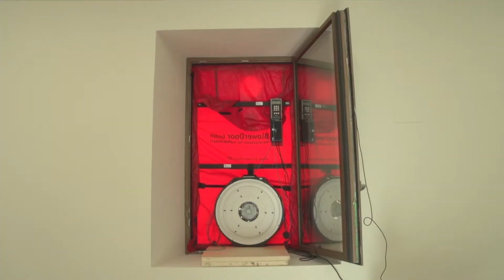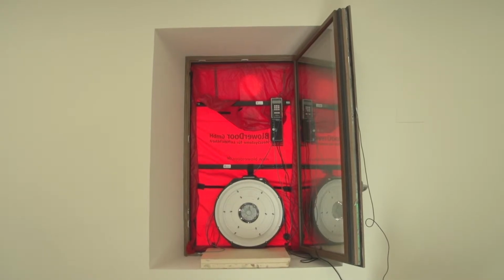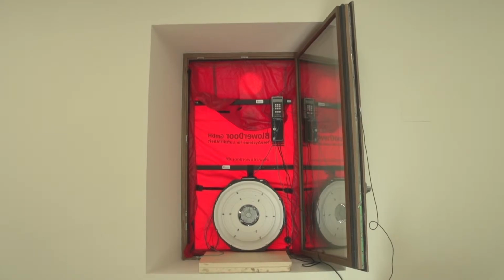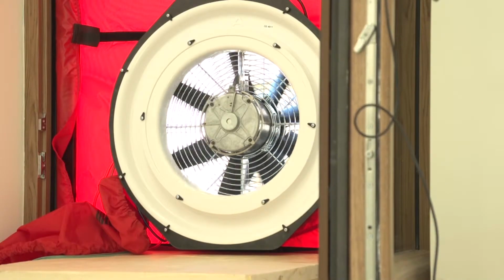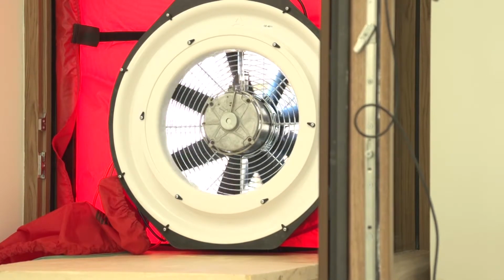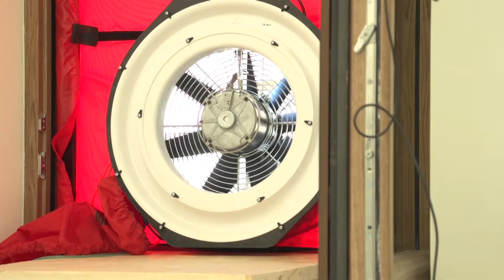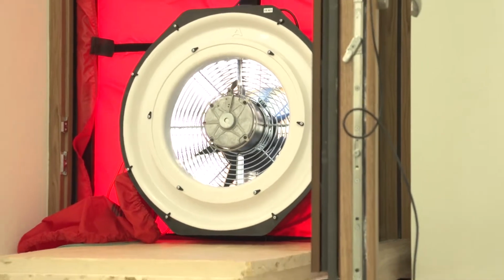To conduct a blower door test, all the building's natural air entry points are sealed: gratings, siphons, and all windows and doors in the envelope. Interior doors are left open. Next, a big fan is installed in one of the openings in the facade, and the rest of the opening is covered with a tarpaulin or the like.